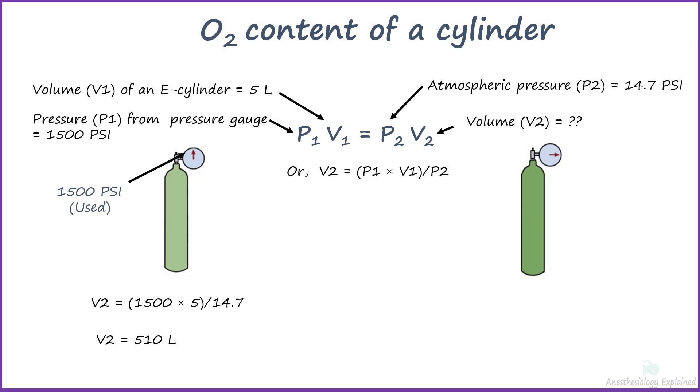There is a linear reduction of the oxygen volume as a full type E oxygen cylinder at a service pressure of 1900 to 2000 psi contains 660 to 690 liters of oxygen. In the earlier slide, we calculated 510 liters as the amount of oxygen left in the E-type cylinder with the pressure of 1500 psi.